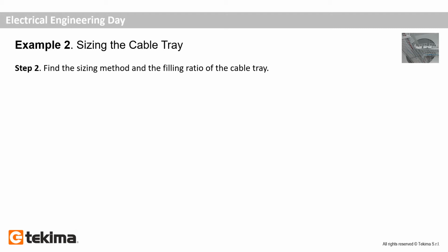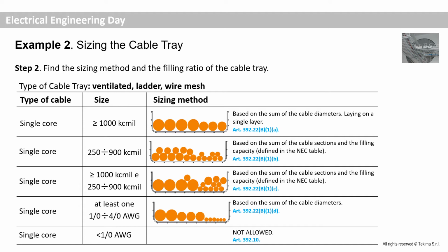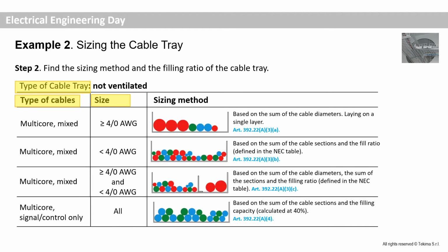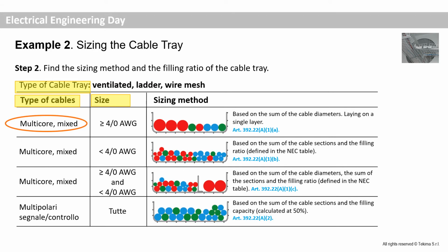And this process is completely different with respect to the raceway. The rules that we have to follow are contained in Article 392 of the National Electrical Code, NFPA 70. The National Electrical Code defines different methods of calculation depending on the type of cables contained, the size of the cable, and the type of cable tray selected. So it specifies the rule, for example, for ventilated ladder or wire mesh containing single core cables, it defines the rules for not ventilated cable trays containing multi-core mixed cables, but it also defines the rules for multi-core mixed cables installed in ventilated ladder or wire mesh cable trays.